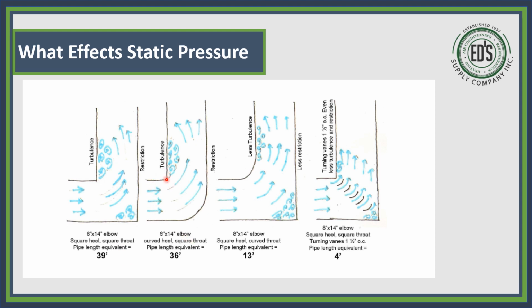If I take a square throat and a radius heel, that's equivalent to 36 feet of duct. But if I take a radius throat and a square heel, 13 feet of duct, because the air blows in at an angle like this, and you'll see turbulence here just like this line's showing. But if I have turning vanes, it's equivalent to 4 feet of duct. Keep that in mind when you're installing your ductwork and your duct systems, because on round pipe, you want to have a round throat, round heel, and you're going to get the same result.